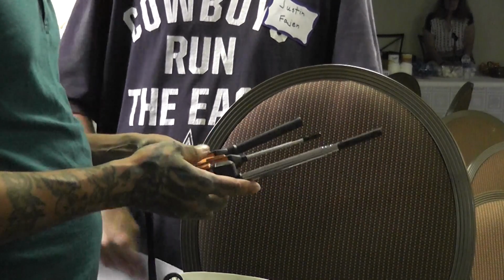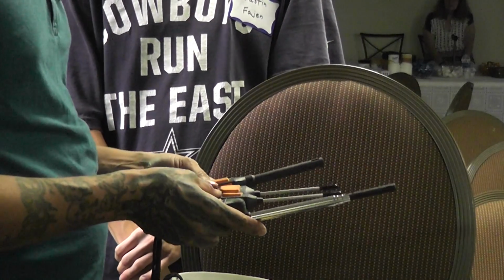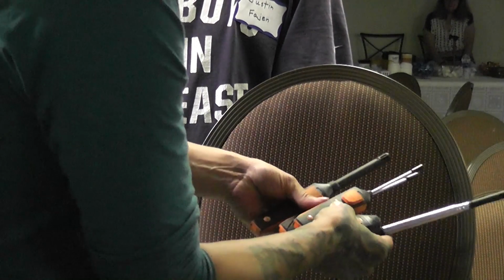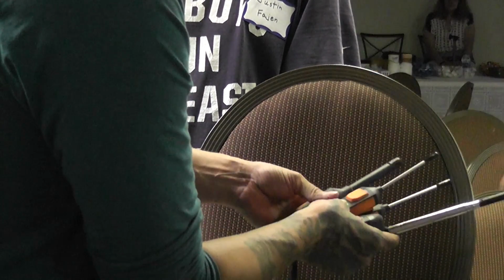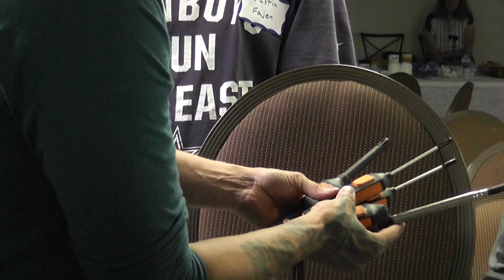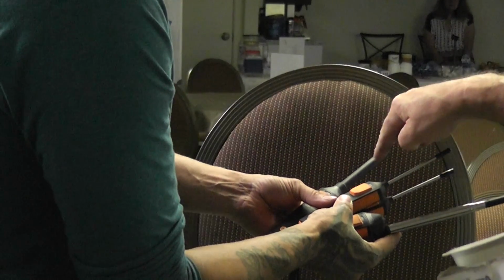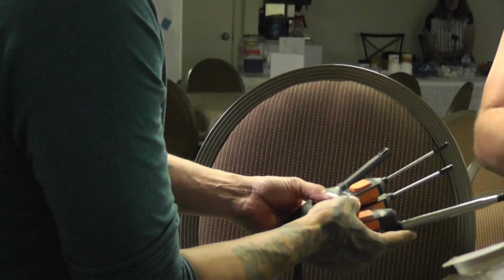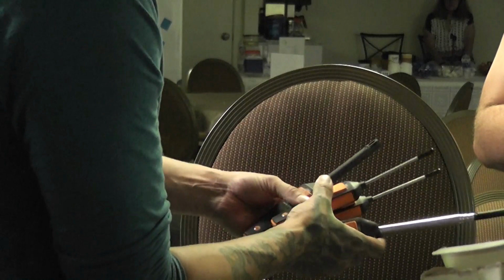That's because you're up there. You're supposed to be down here. So, the difference, I know these two are the same, correct? Difference between the three. I'm gonna look and see relative humidity, temperature, air velocity, just the temperature. I can almost tell you when it's gonna rain. Nobody put the filter back in, so will that make a difference? No, you better to take all the readings without it.